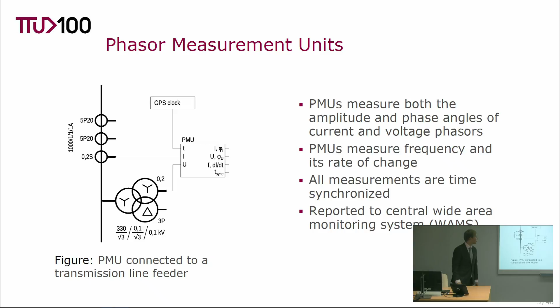As the name implies, phasor measurement units measure both amplitudes and angles of current and voltage phasors. In addition, they measure frequency and the rate of change of frequency. The measurement data is time synchronized and reported to a central wide area monitoring system. Here we can see an example of a PMU connected to a transmission line feeder, with a time source and current and voltage signals from the current and voltage transformers.